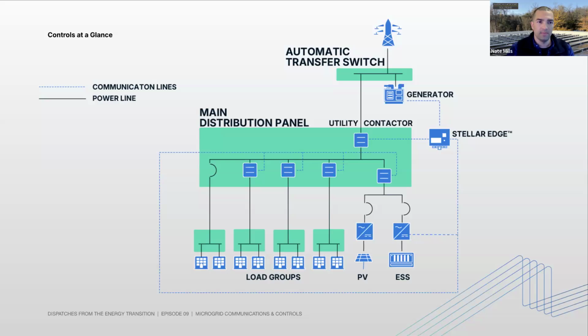The point I'm trying to make is that when we talk microgrid controls, there are multiple levels of control systems throughout the system. The battery alone will have the BMS on the battery modules themselves, the inverter will probably have some kind of native EMS associated with it, and the Stellar Edge is really a site controller, coordinating multiple assets across the system and optimizing their performance. So when the grid goes down, we've got the solar providing power to the main bus and then to the loads.